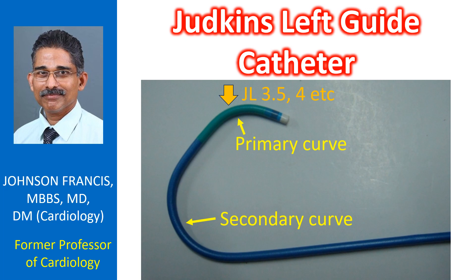Guide catheters are stiffer due to their braided design, and the lumen size is larger than that of diagnostic catheters. The tip of guide catheters does not taper like that of diagnostic catheters.